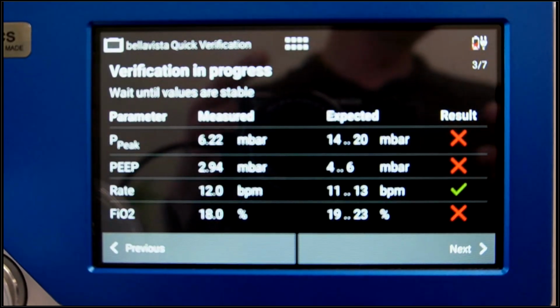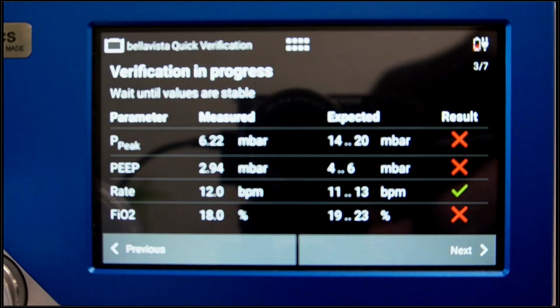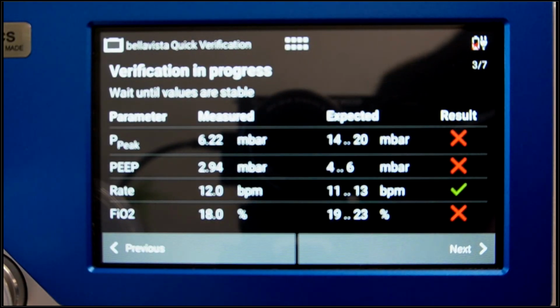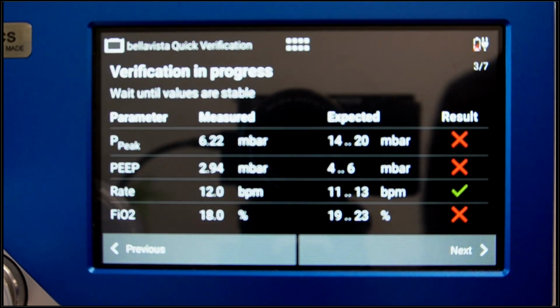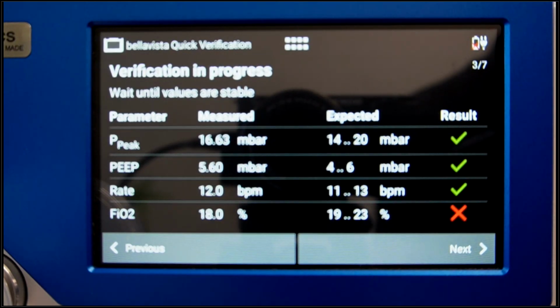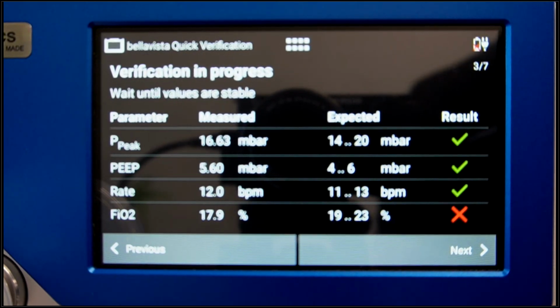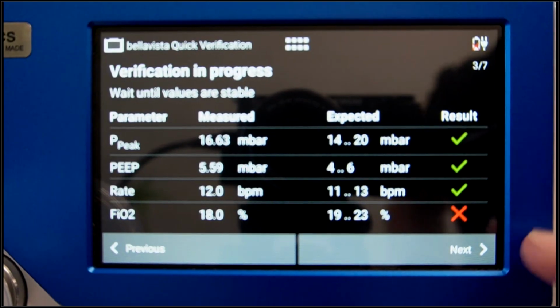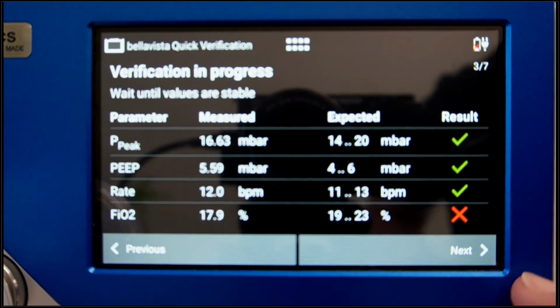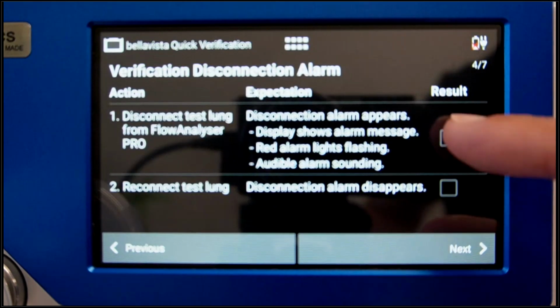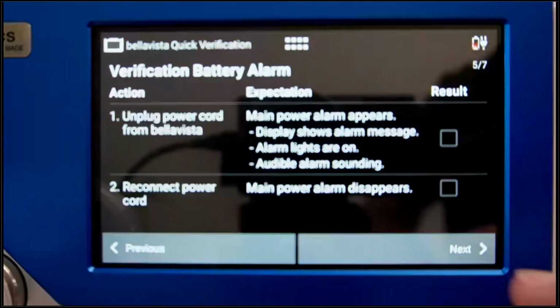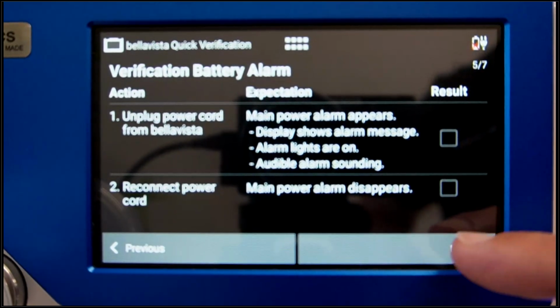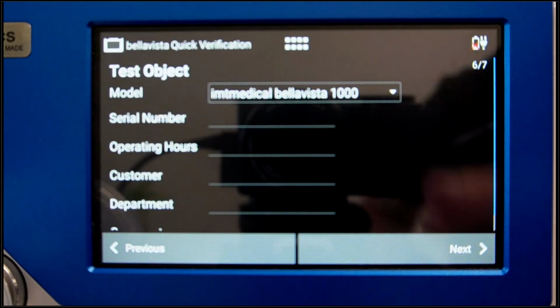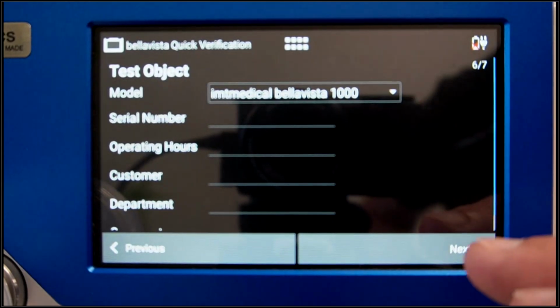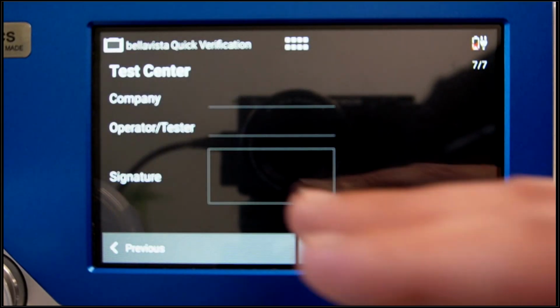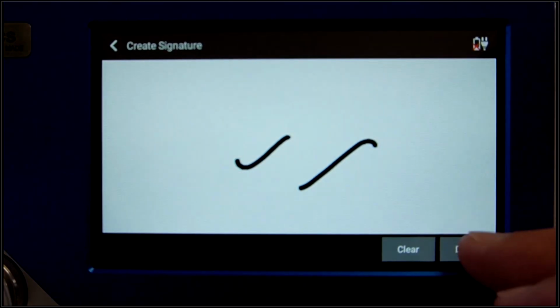When it comes to take measurements, these apps know actually which parameters we need to test, and it knows the expected ranges. It can also calculate sometimes expected ranges. With some ventilators, this is based on an actual measurement. So it does that automatically and gives you pass-fail criteria on the screen. Sometimes it's just to confirm things. It depends on the exact procedure of the manufacturer. At the end of the application, you can then add information about your device under test and about yourself, and you can even sign a report here.